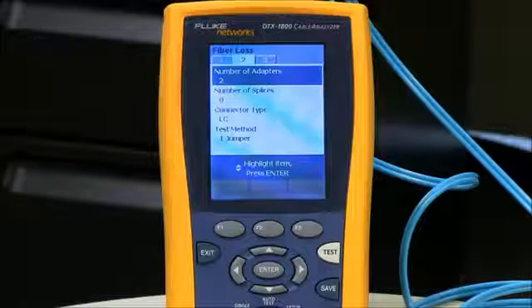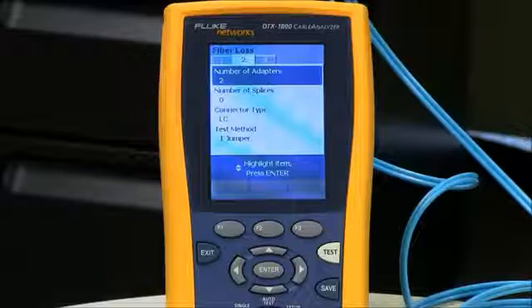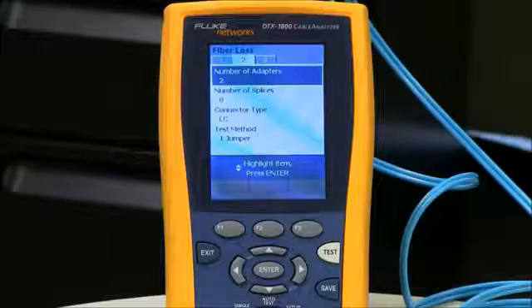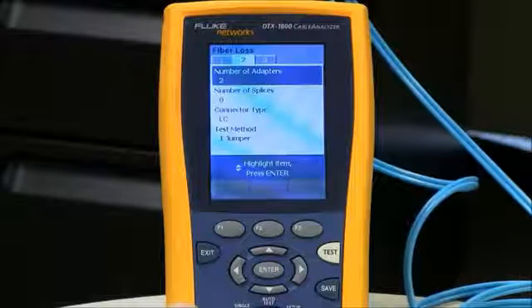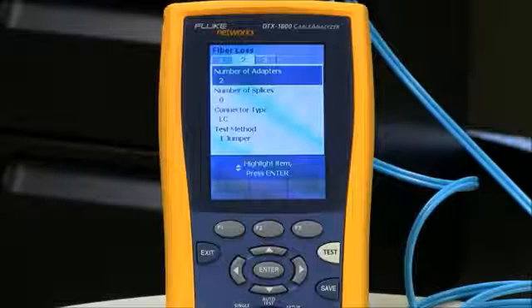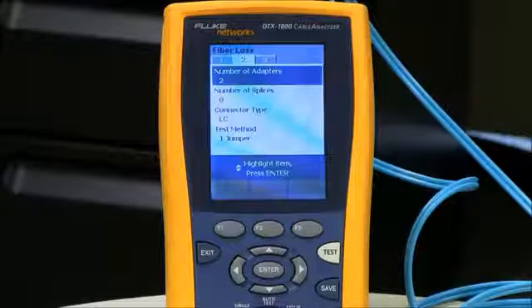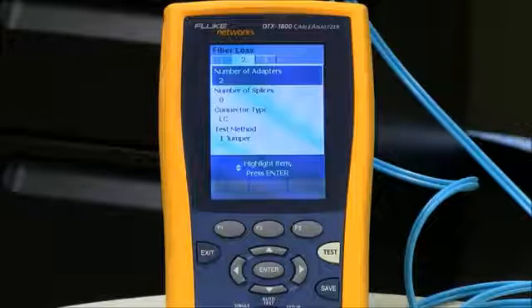My number of splices is zero, even though I'm using mechanical connectors today. And when I say mechanical connectors, I'm talking about types such as the Unicam, which have a mechanical splice inside. That's part of the connector. You do not add an extra splice count in there for each of those connectors. My connector type is LC. That's not going to affect the outcome of the test result. That's just going to affect the help screens on the DTX cable analyzer.